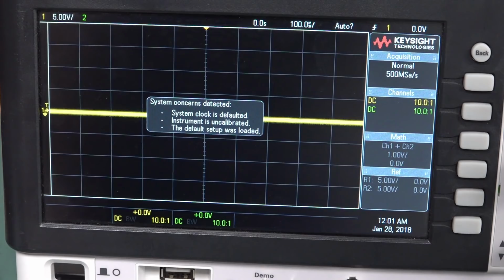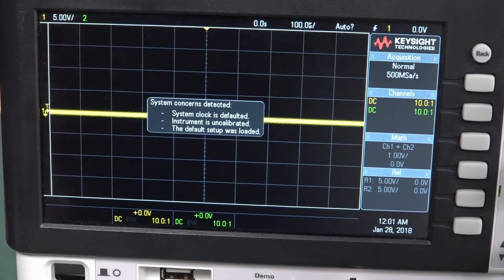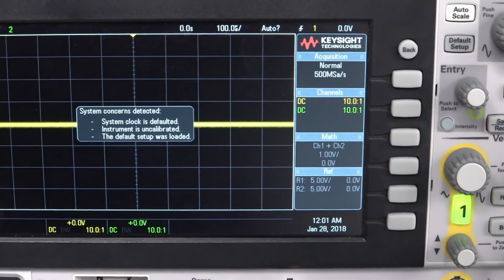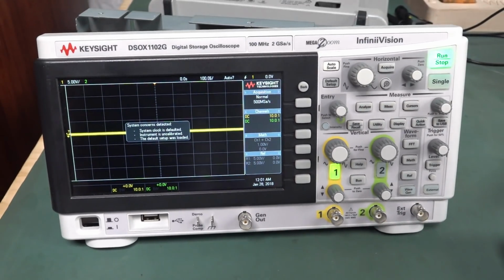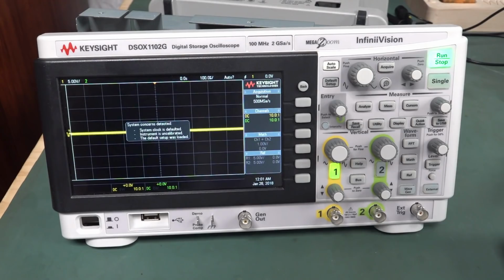And look, it's obviously detected that change, because we never had this on boot up before. System clock is defaulted, instrument is uncalibrated, the default setup was loaded. So that's promising. So maybe this could be as simple as I was simply tweaking, fiddling with. Don't twiddle with your knobs, let me tell you. I was fiddling with my trim pots. And maybe I completely and utterly screwed it up and put it into some mode that it didn't like, and that corrupted the default boot up and maybe the calibration, although it shouldn't, but you never know.